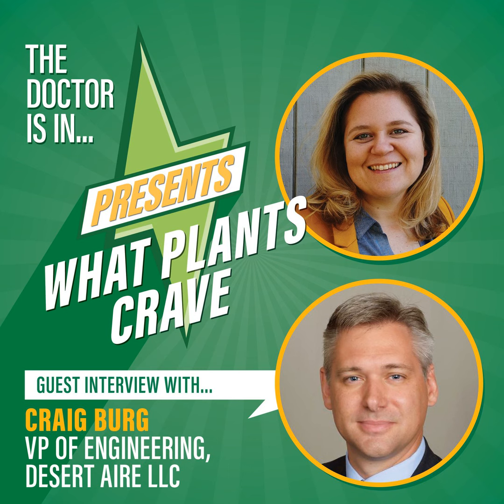That has a different effect, and it can cause more wear and more potential risk for some system components. So as nice as that package system was, maybe that's an area to think more about using a split system instead, where only the remote condenser and some fans are on the roof, or even better, at grade level outside, so we can go look at them, shovel them out in winter, whatever it may be, since we're running 24/7, 365. So it starts there too. We have to be careful about what type of equipment we're applying in what locations.